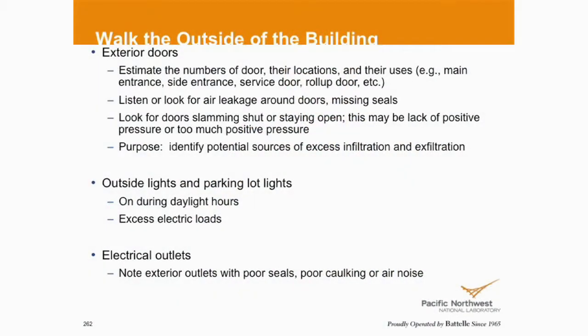It's problematic in large buildings because of stack effect, and sometimes you can't do anything about it. But I'm saying most of your buildings here, stack effect probably isn't going to be an issue. Windy days, it's not a good time to check because you're never going to get a good reading. So calm days, check your building, see if you've got any infiltration going on or excessive exfiltration. We don't want doors slamming open or closed. We don't want to hurt students.